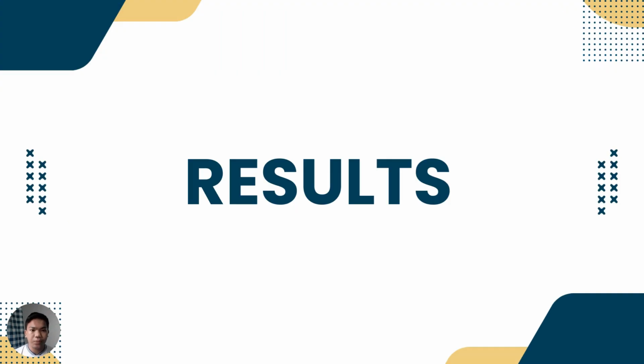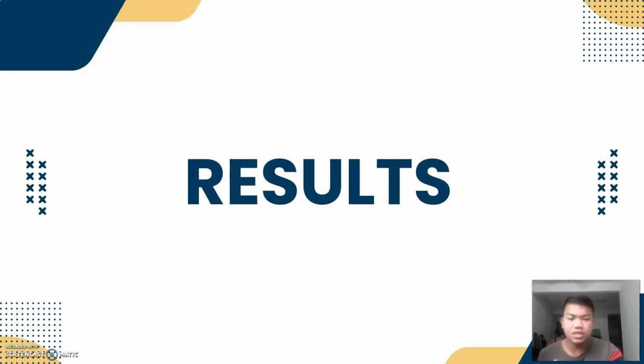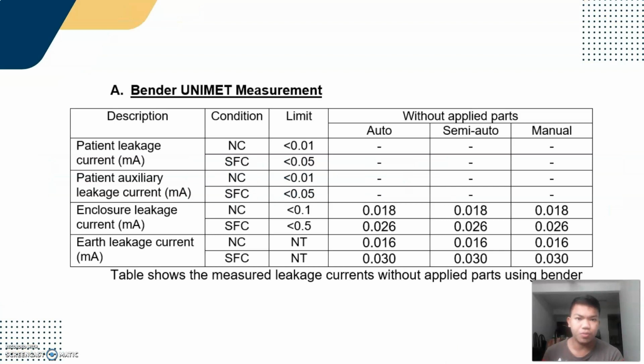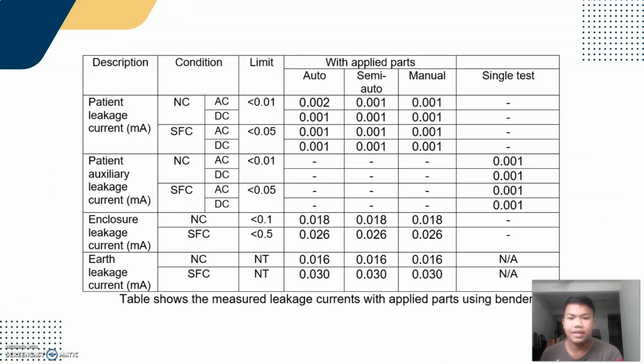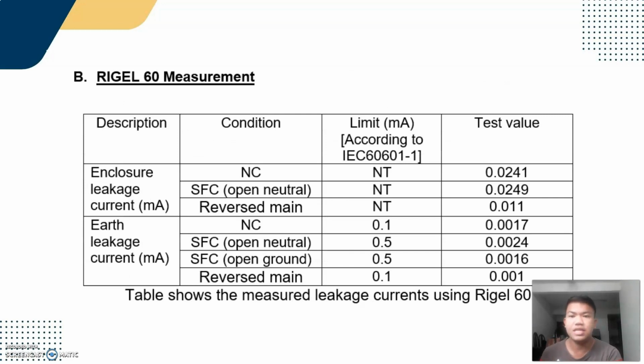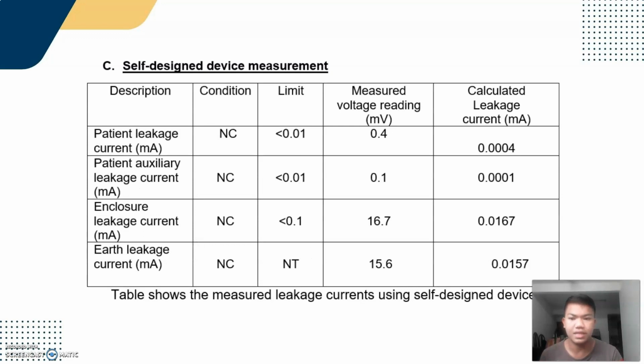calculated using Ohm's law, V equals IR, to obtain the leakage current value. For results, this is the measured leakage currents without the applied parts using the Bender, and this is with the applied parts using the Bender. For the Rigel 60 measurement, this table shows the measured leakage currents using the Rigel 60, and this is the results of the measured leakage currents using the self-designed device.